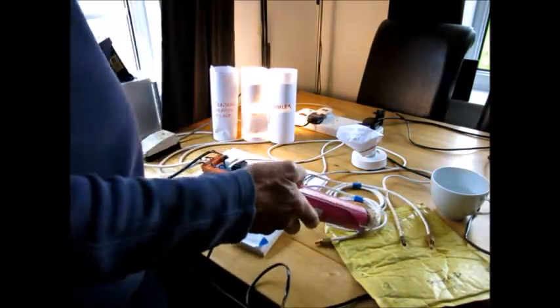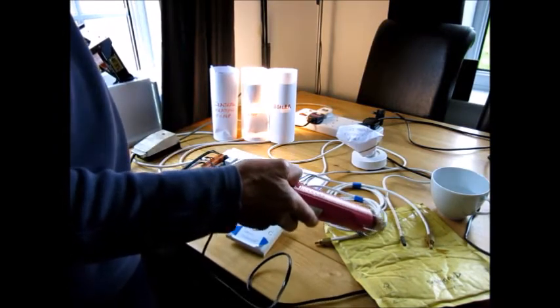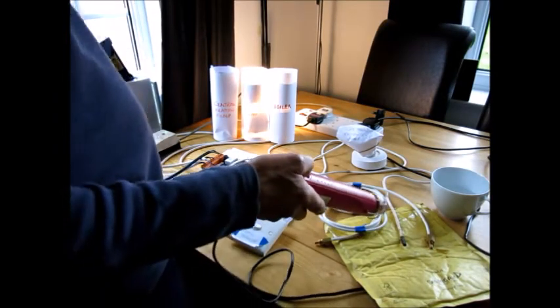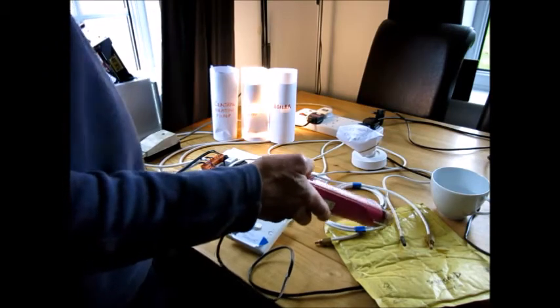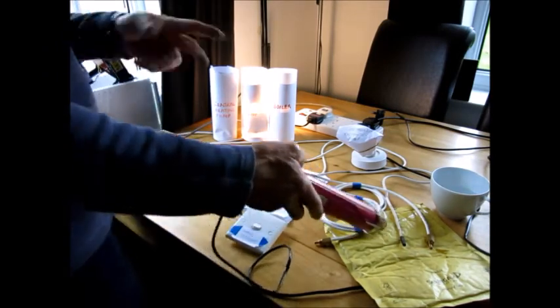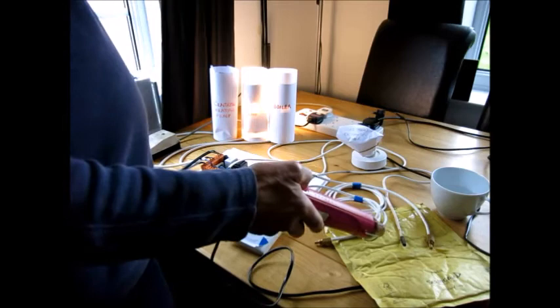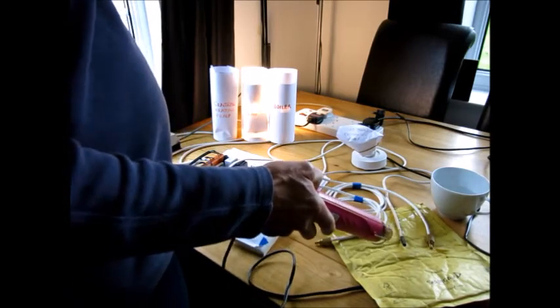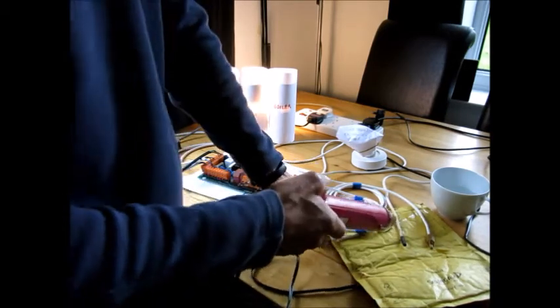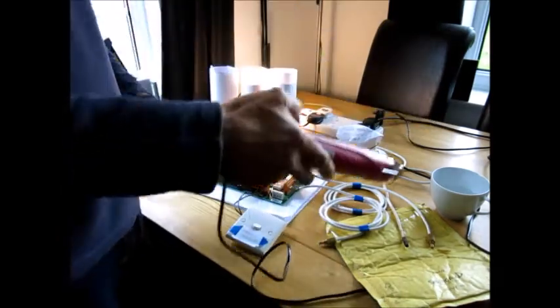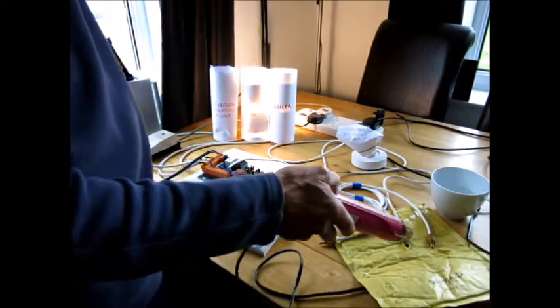So I'm still just going to keep this topped up around the 80 degree mark, and you'll see this boiler pump go off in a minute. I'm not going to turn the heating thermostat on because that will reset the timer. So I'm just going to keep this warm about the 80 degree mark. Like I say, this bottom thermistor down here, the one that's at the bottom right hand of the cabinet, it doesn't actually get too involved.